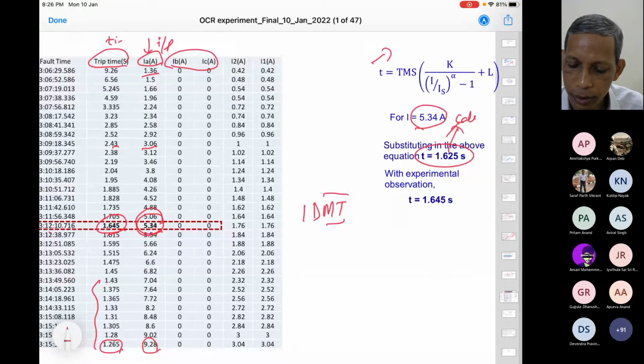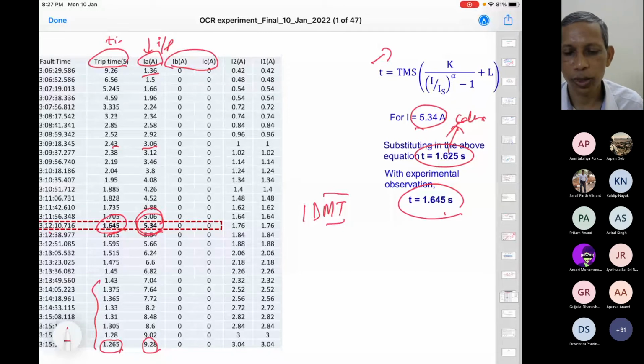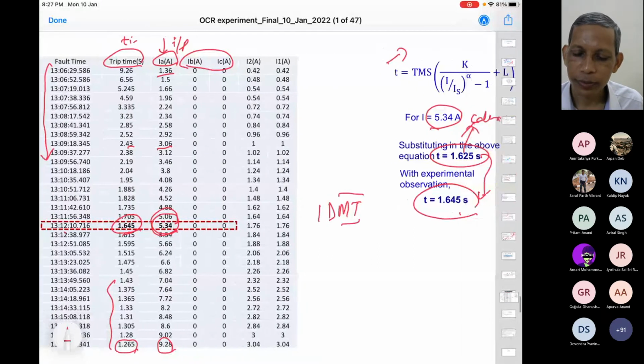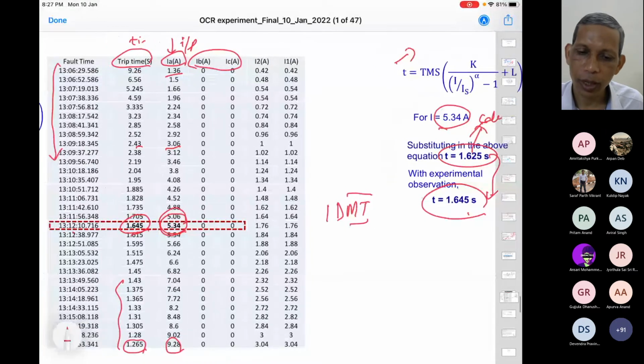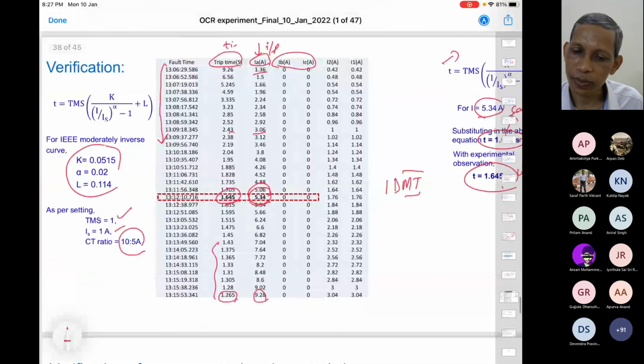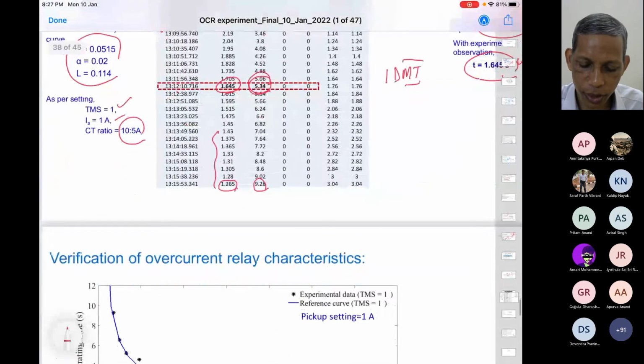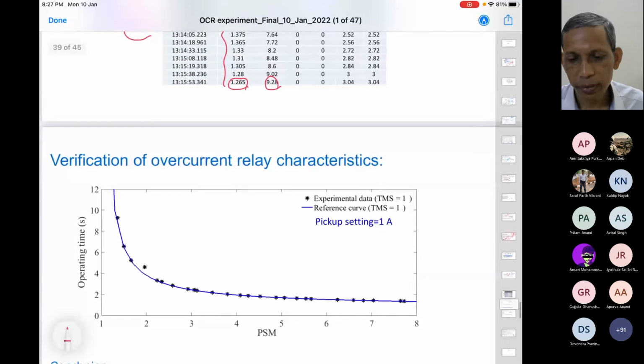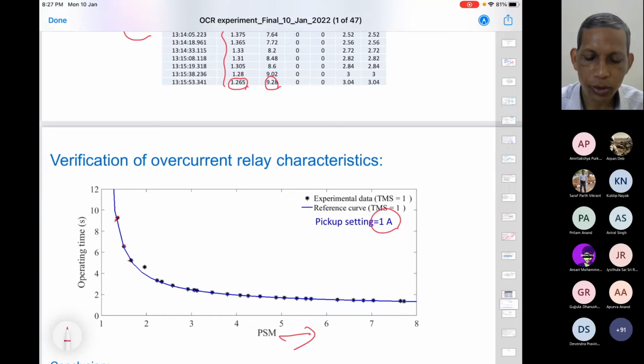That is the calculated, simulated value. But the actual one from the laboratory, from that injection of current, is noted as only 1.645. So there is some discrepancy. Those are factors such as circuit breaker opening time, uncertainties in the measurements, and how good our CT ratio is. We are talking about 10:5, it may be something different. So for this case, these are the current divided by the pickup setting, where pickup current is 1 ampere. We got these points, which are in this table, and the solid line is the reference curve you get from the equation data.